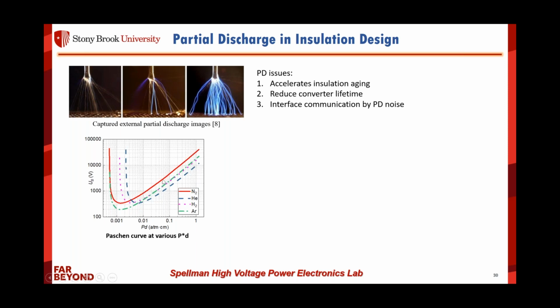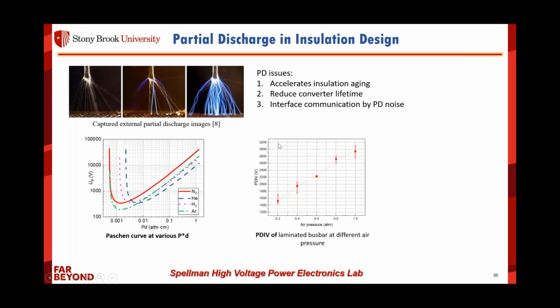Such a curve is called Paschen's curve. Only when you go beyond a certain point, more like running into vacuum, will your breakdown voltage go up again. Our job scope here is trying to understand the consequence of such a design and how to achieve a PD-free or PD-less design for my system.